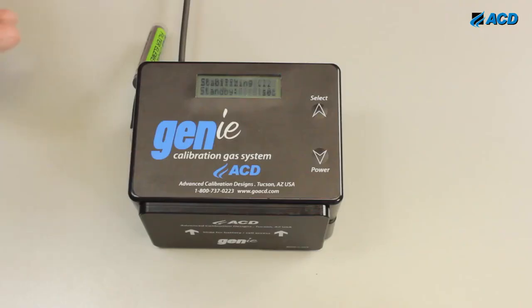So it's going to show me I've got 50% life. You know, the pump ramping up because I ask it for 1 liter a minute. It's going to count down for 20 seconds, and then it'll be stabilized, okay? All right, so then you'll see it now. It locks in, 5 parts per million chlorine. We can go calibrate everything we want to.